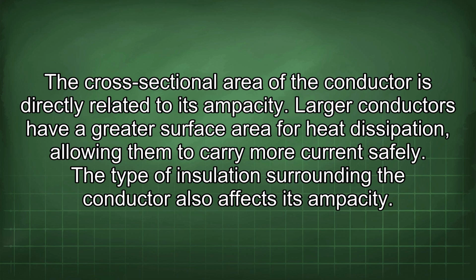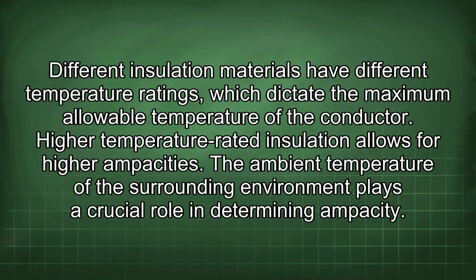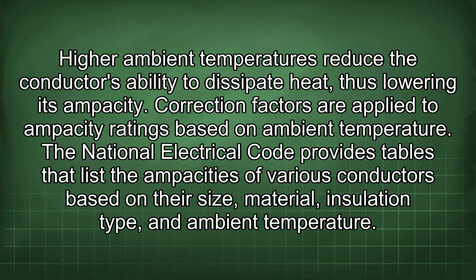The type of insulation surrounding the conductor also affects its ampacity. Different insulation materials have different temperature ratings, which dictate the maximum allowable temperature of the conductor. Higher temperature rated insulation allows for higher ampacities. The ambient temperature of the surrounding environment plays a crucial role in determining ampacity. Higher ambient temperatures reduce the conductor's ability to dissipate heat, thus lowering its ampacity. Correction factors are applied to ampacity ratings based on ambient temperature.